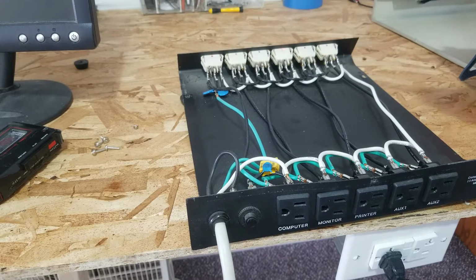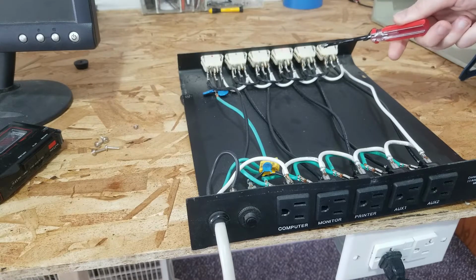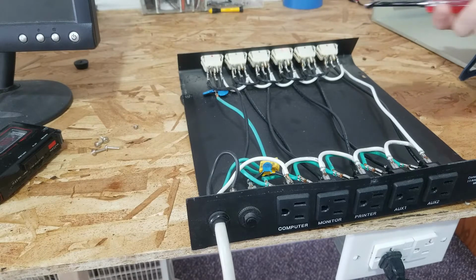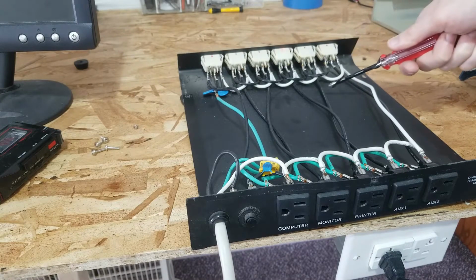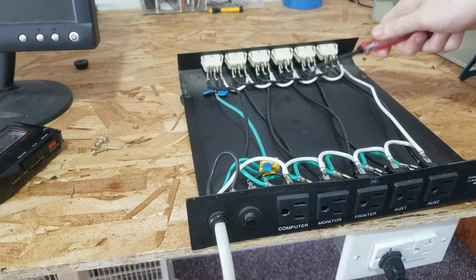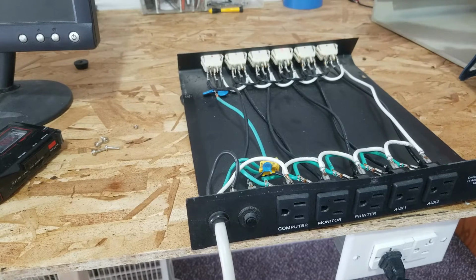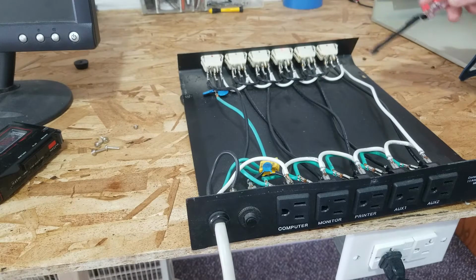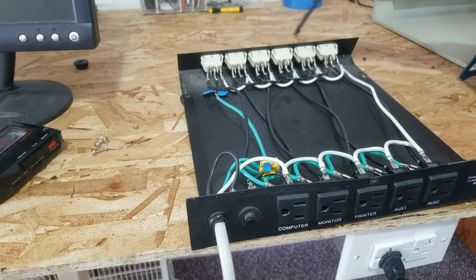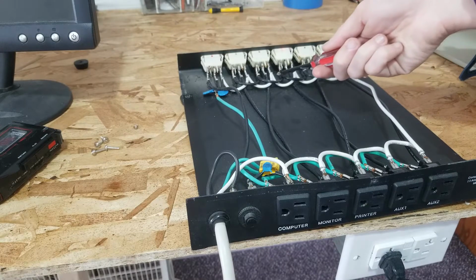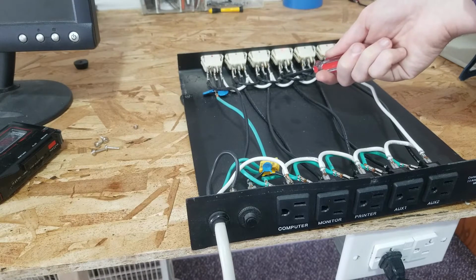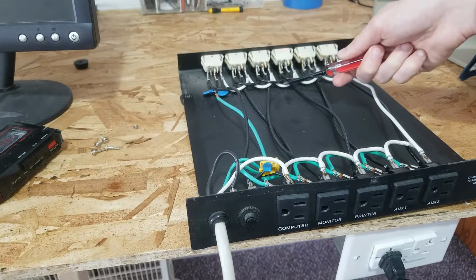So what I think happened here, because it happens occasionally, it is the switch. I switched it on, and instead of connecting the lives together properly, it either does one of two things. One, it also connects the live here to the neutral here, which shorts it out. Remember, this neutral here is supposed to be for the light inside it, so it can complete the circuit with the light on. So it switches this contact here, the live coming in, to both the live and the neutral.